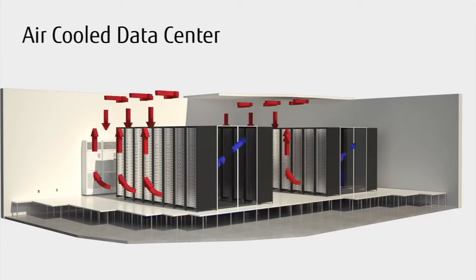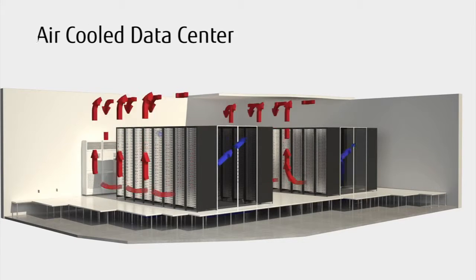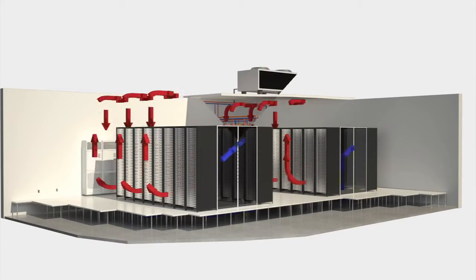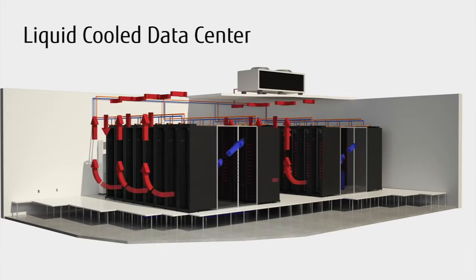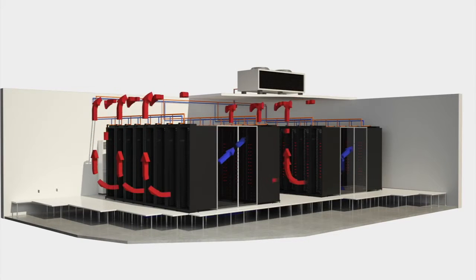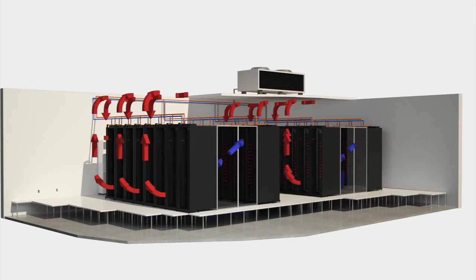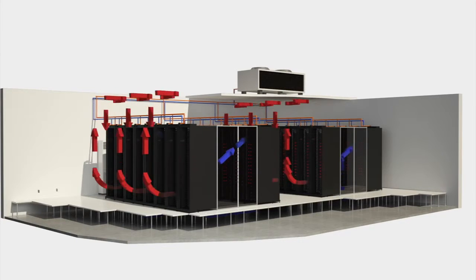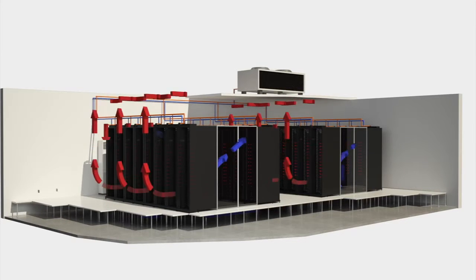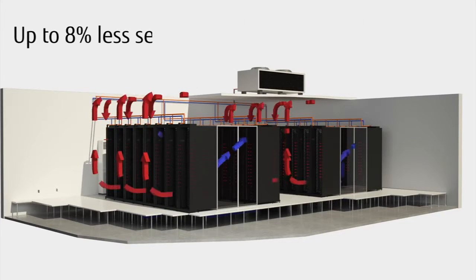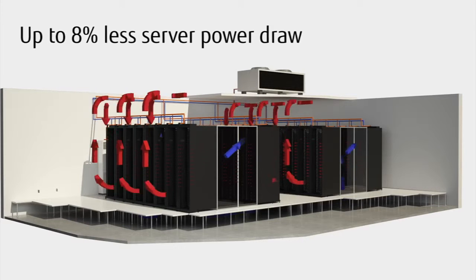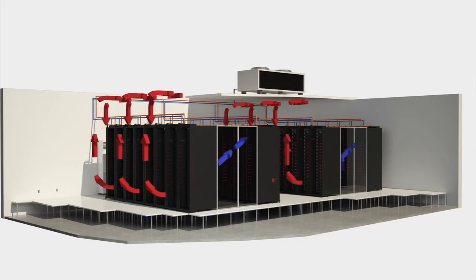Back in our air-cooled data center, we need much less cold air to run servers comfortably. This is because air is only cooling components that don't generate much heat. This has 2 important impacts. First, less air conditioning is needed, reducing the energy used to cool the data center. Second, the server's fans run slower, which leads to 8% lower total power draw.